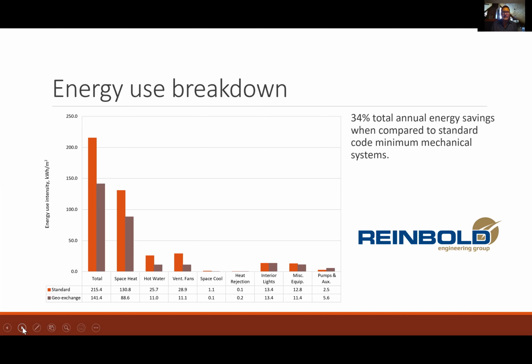And the reason for that, which I didn't explain, is that in Spring Creek, one huge advantage of using the groundwater is we do not run it through the Geo Exchange, because we have what's called free cooling. We can take this groundwater at 7-10 degrees and bring it right up. We don't have to run it through the compressor. We can run it straight to a plate exchanger and use that as our cooling water for our air conditioning for all our buildings without any compression. It's just running the pump to circulate the water through a plate heat exchanger. It gives us that free cooling, which is a huge cost savings.